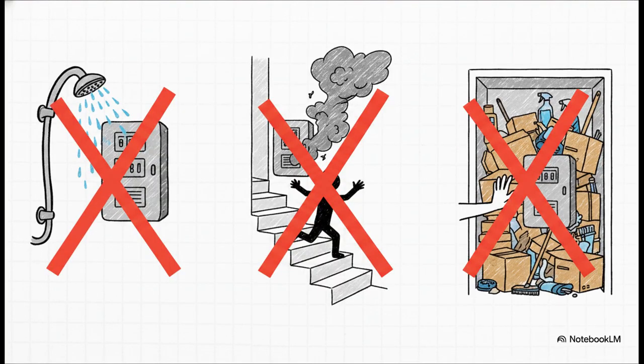So the crucial point is that a command center is really only as good as its location. The standard gives us a strict list of forbidden zones. You can't put a switchboard near baths or showers, what we call zones 1 and 2, because high humidity and moisture are the mortal enemies of electrical safety. You can't put them inside fire-isolated stairways either, because if a fault in the board creates smoke, it fills the exact path people are trying to use to escape. And you definitely can't just shove them into the back of a cluttered cupboard. If they're in a cupboard, they need dedicated, front-facing space. Clutter is a massive hazard here.